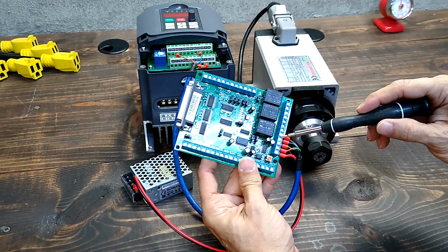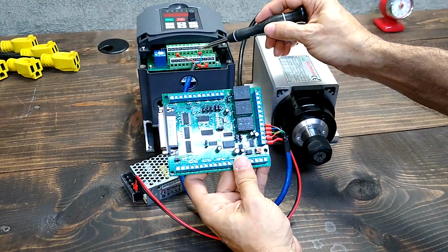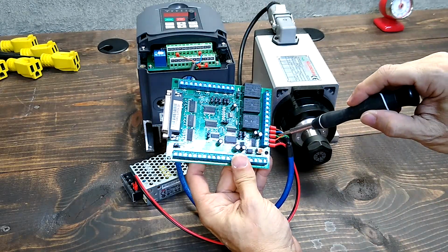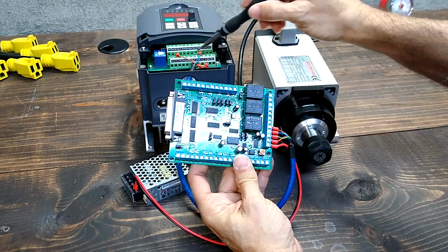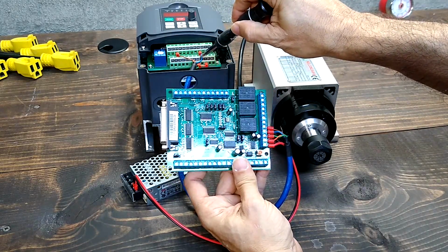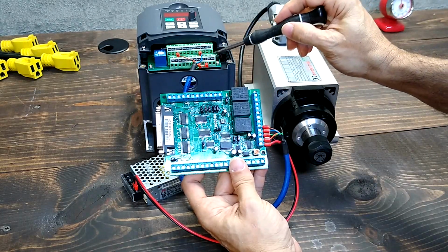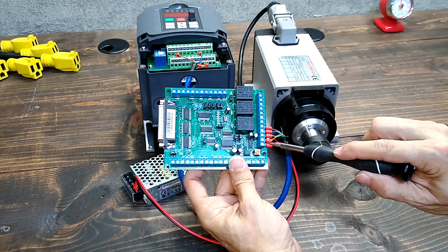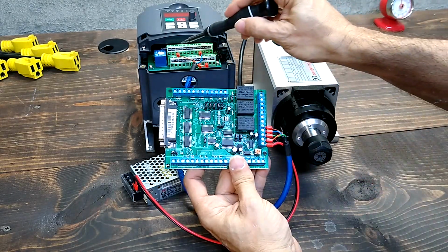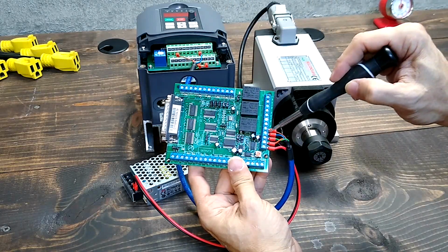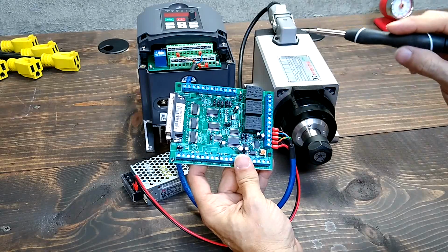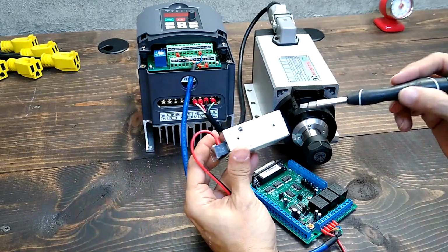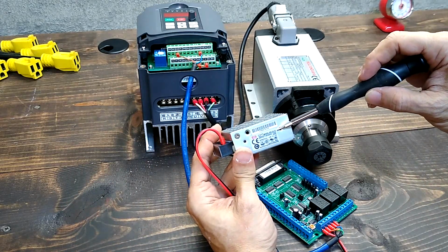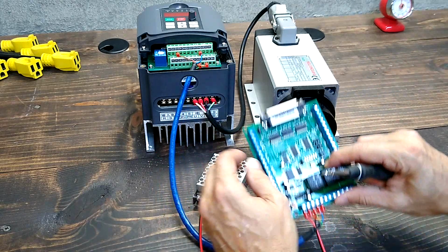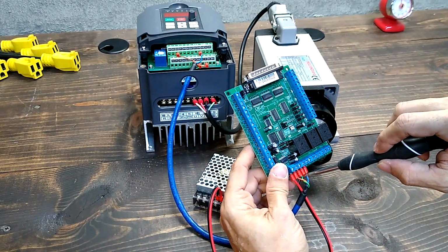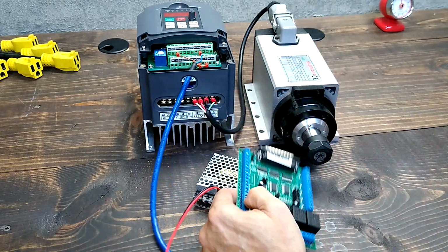We will connect normally open of relay 1 to forward, ground to ACM, voltage in into 0-10 volts, and DCM to voltage in of relay. We must connect a 12 volts power supply to 12 volts terminal of C11G board and ground, making it common with a VFD ACM terminal.